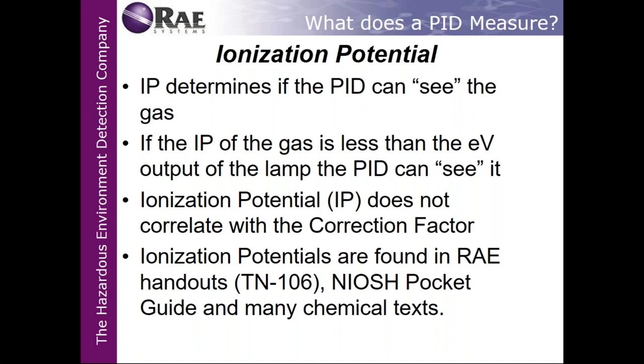The correction factor on a 1.0 scale for acetone is 1.1. So if your monitor's reading 10 and you have it in isobutylene units, you take 1.1, you multiply it by 10, which comes to be 11. So it's very simple math if you use base 10. It's easy for me to use that way to explain how a correction factor works.